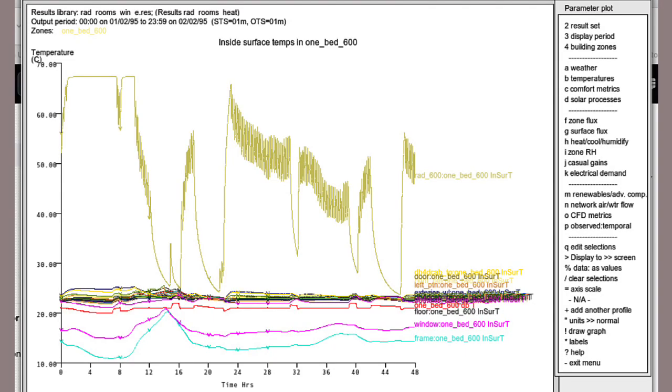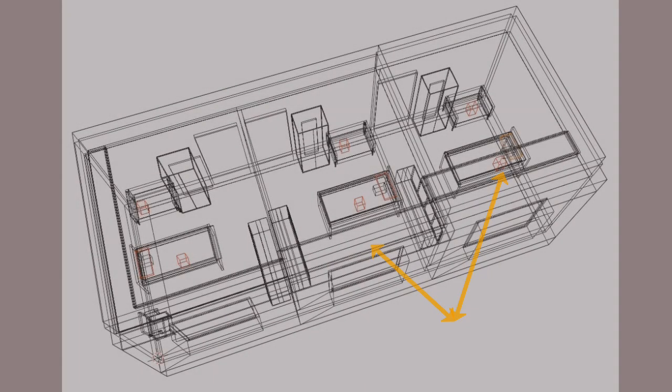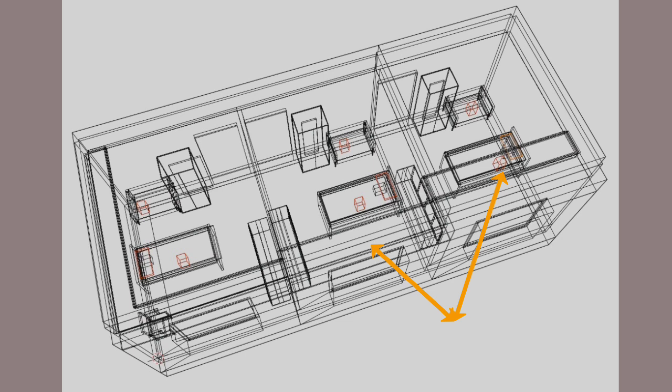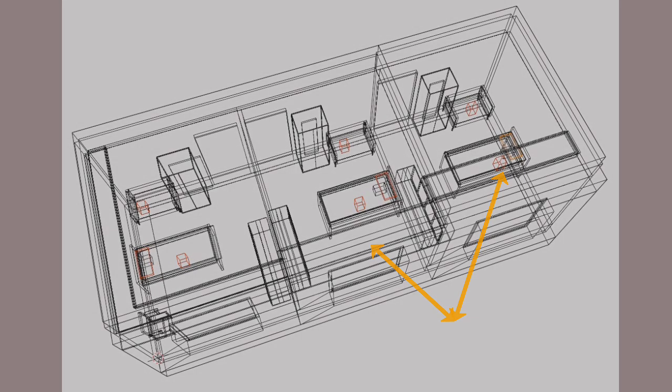Changing focus to the middle room with the simple single panel at the facade. A lot of the patterns are very much similar, except that because the panel is slightly smaller, it's needing to run at a higher temperature in order to maintain temperatures within that zone. The third room is one of those classic, what if we shift the panel to be closer to the people in the room?